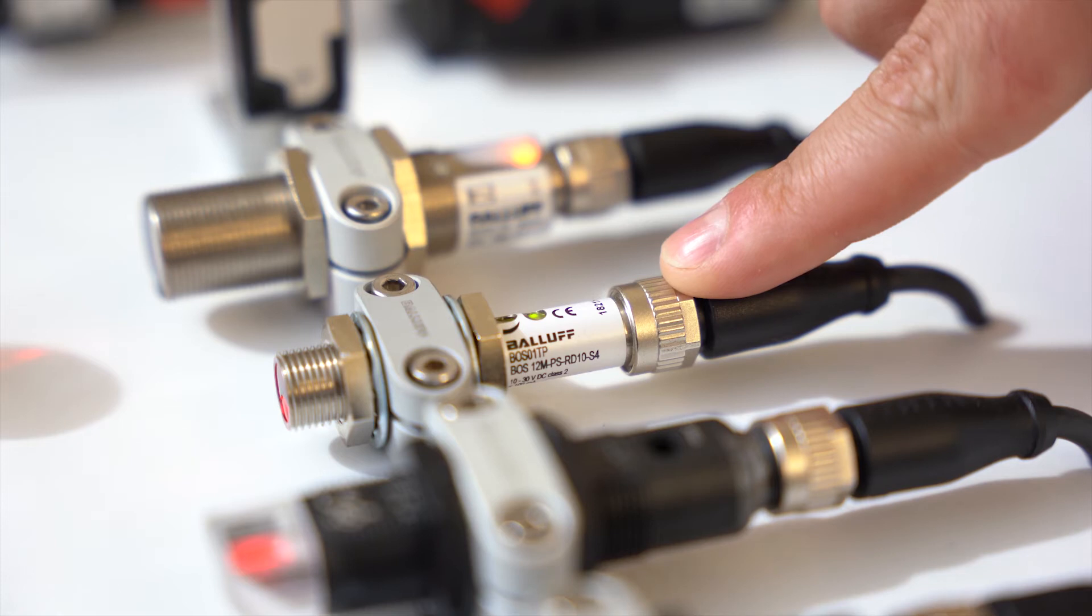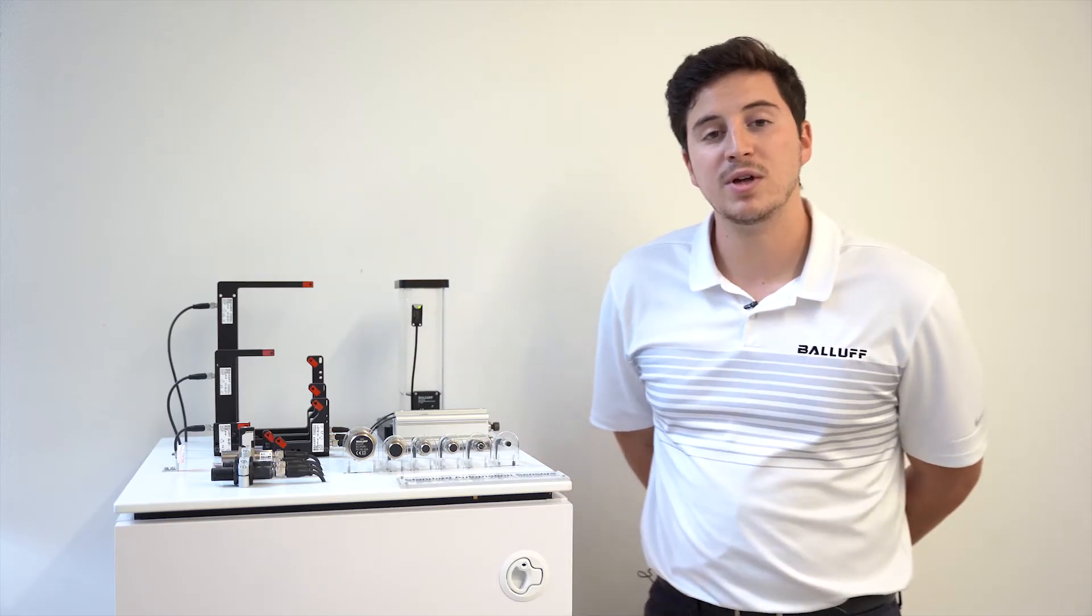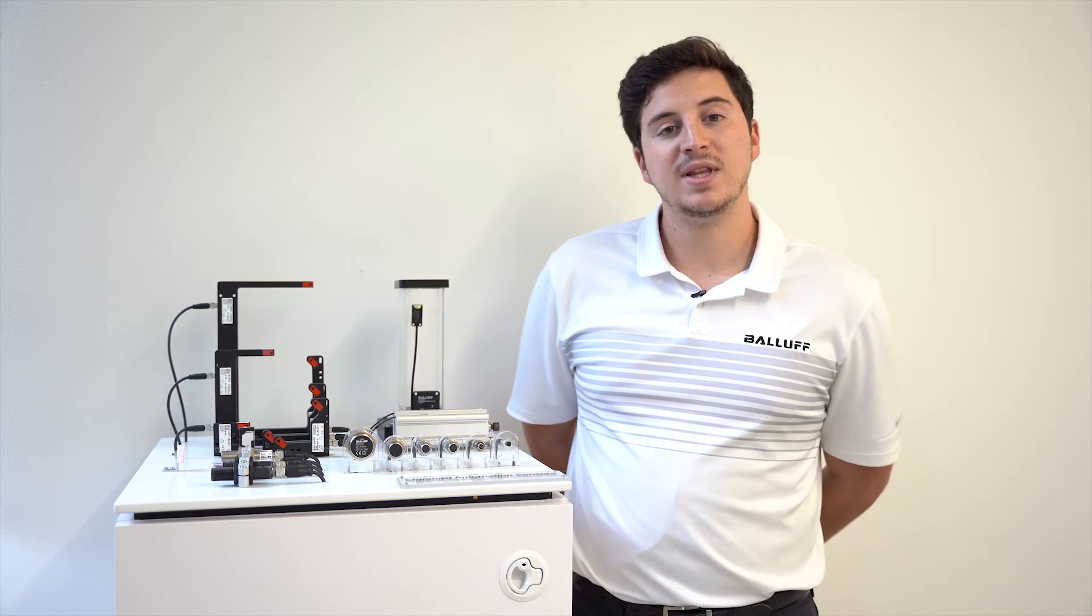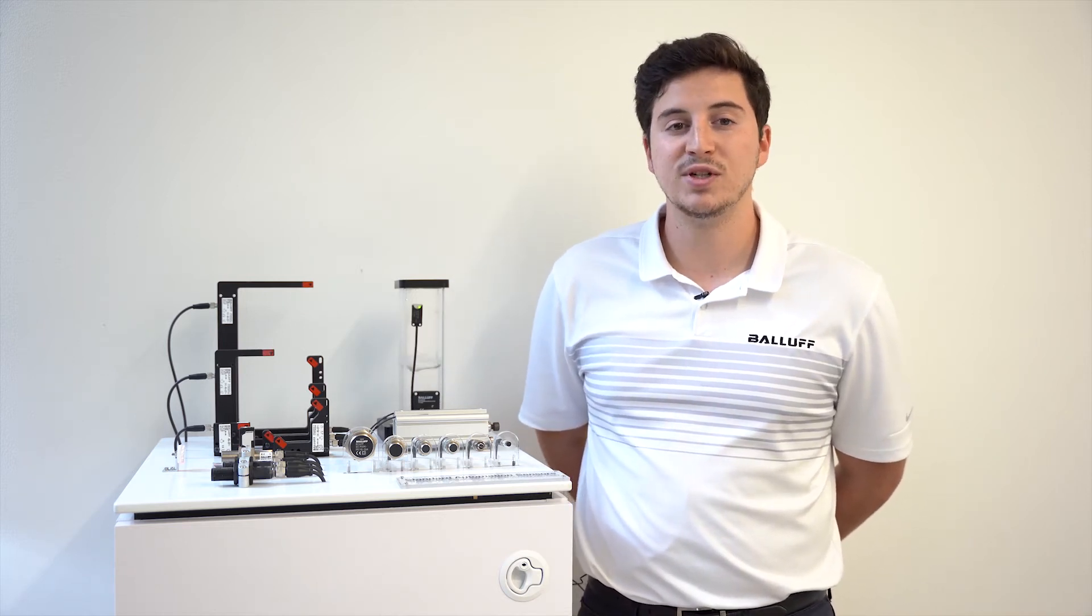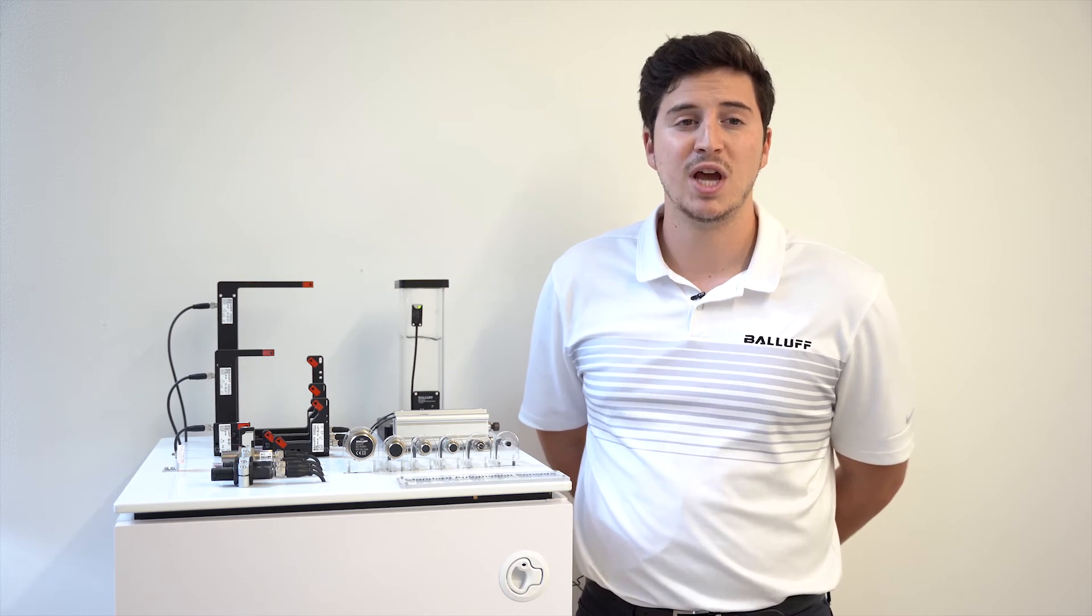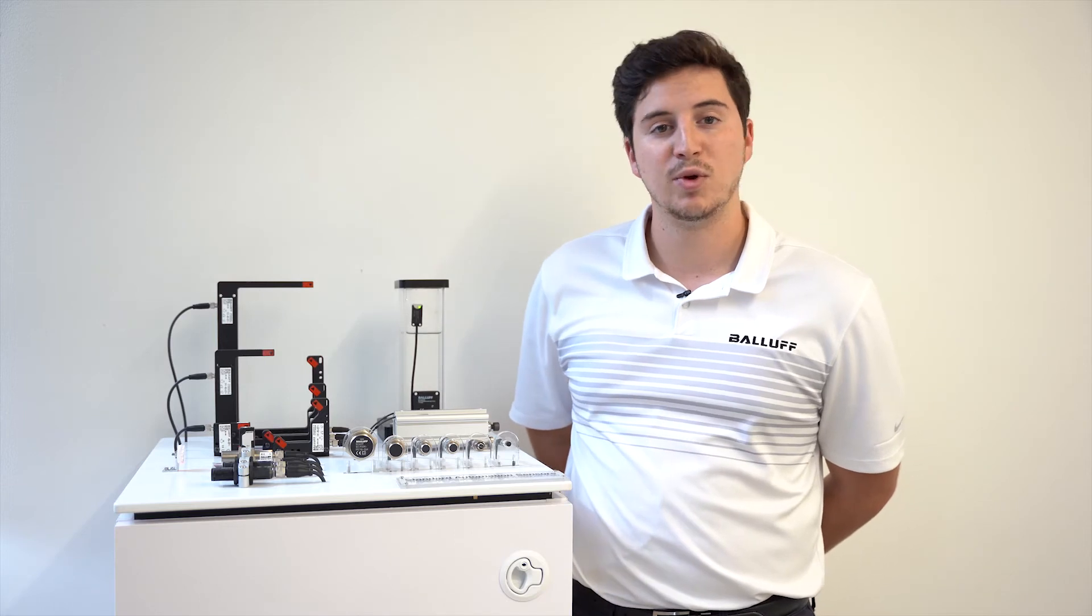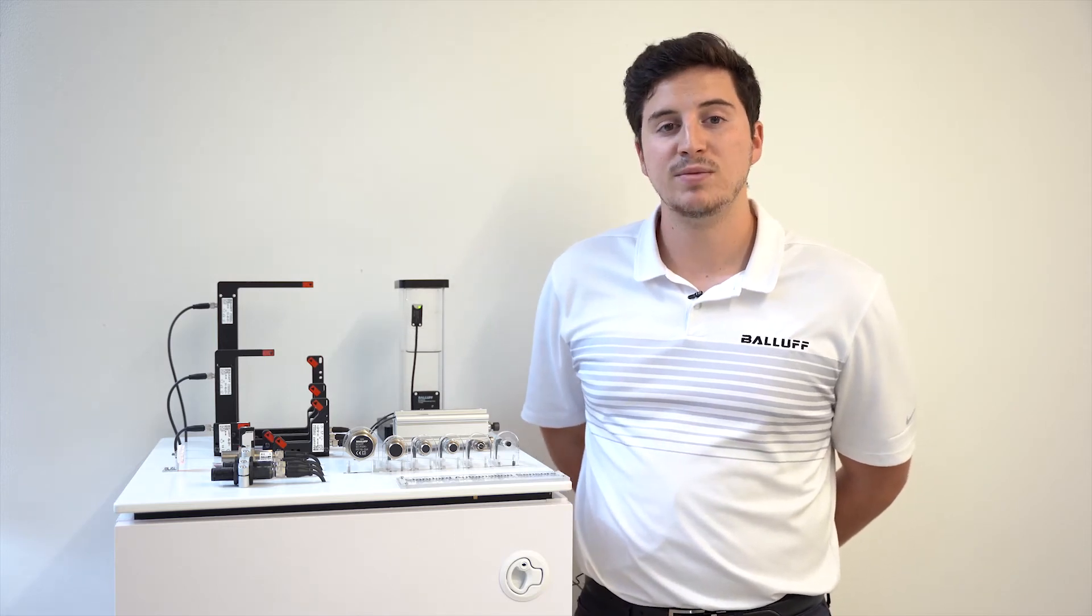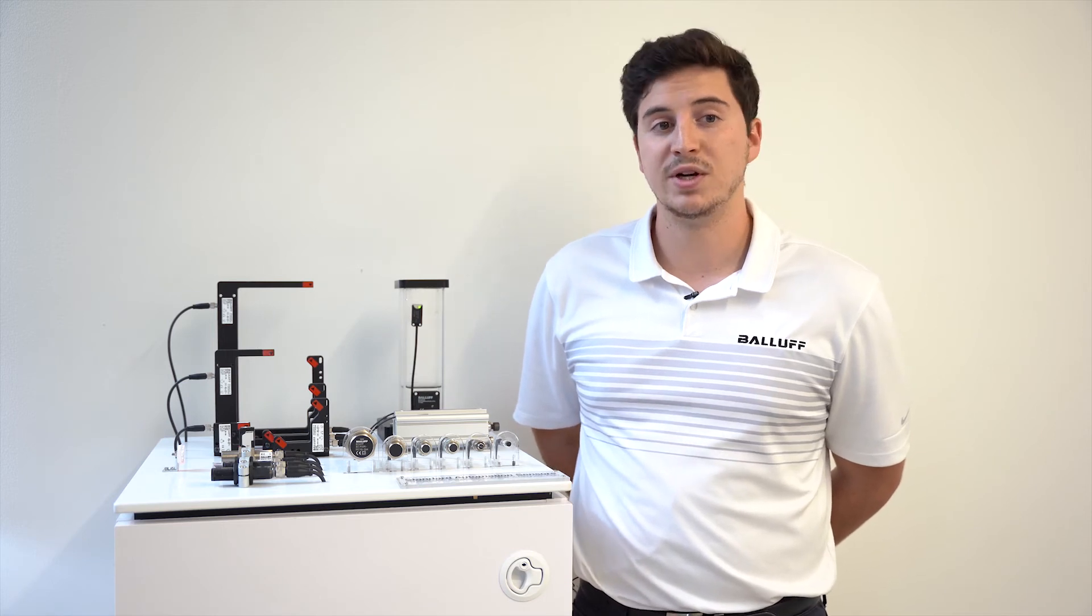The last diffuse photo eye is a diffuse sensor with background suppression. So it works similar to other diffuse sensors, but it can also detect objects with a teachable switching distance using what's called a potentiometer, which is located on top of the housing and is also adjustable. Background suppression provides reliable object detection regardless of surface or material as well.